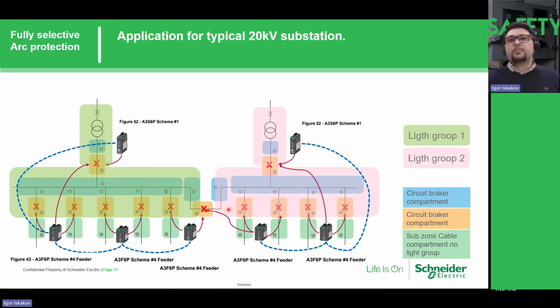For securing the second part, we dedicate our arc flash protection to light group 2, which we can also configure by the DIP switches in the devices. In case we have an arc flash here, any sensors we dedicate will be dedicated to light group 2, and it will provide the trip to the incomer again and to the bus bar circuit breaker. We can use up to 9 different light groups for different applications.